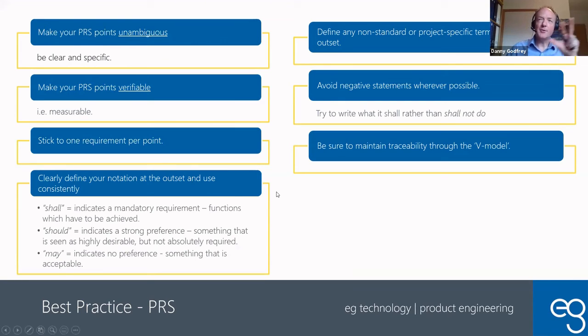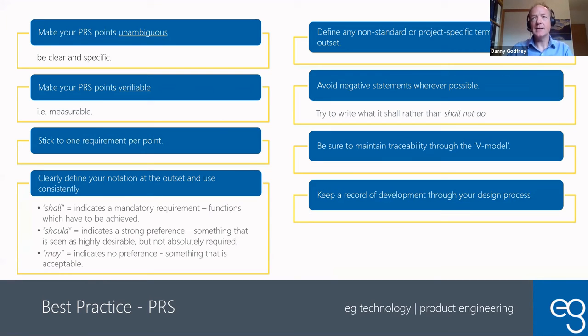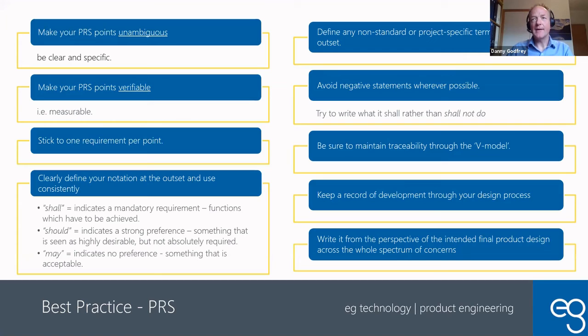Traceability, this is going from user requirements to product requirements. So if your user requirement is shall be desk-based, and that translates into 4 product requirements about footprint and weight and being able to tie it down and so on and so forth, you need to be able to illustrate that to pass that user requirement, all 4 of these product requirements have been designed to and tested. Most importantly, keep a record of everything that you're doing, and always start out by thinking about the final product, even if you're going to go through 3 different rounds of prototyping on the way through, because that way you don't end up backing into a corner, suddenly finding out that you can't add the final thing that you'd forgotten about because it wasn't in the spec. It's fine to have a specification which talks about the final product and then explicitly says, but I'm not going to do that for the alpha prototype, I'm not going to do that for the beta prototype, but it's a good idea to have it in there so it doesn't drop off by mistake.